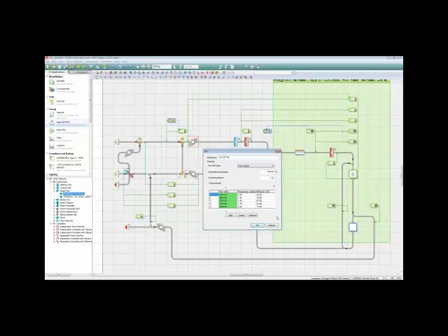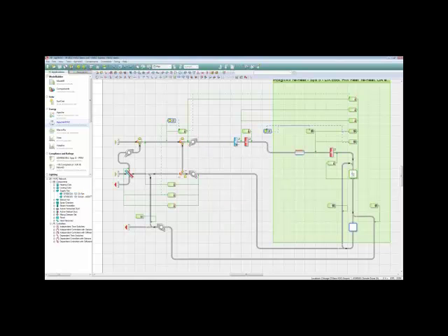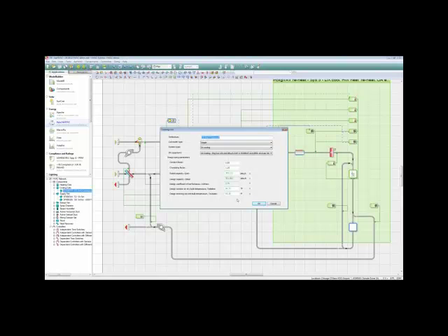So all of the coil sizing is done directly from the process that we just went through, as is the fan sizing. So if I go in and look at this DX coil, for example, it's now got these values, and as I pointed out before, these are now the design conditions for the design sizing of this coil, and you can see that here's the rated capacity at the rated conditions, and this is derived from what I've got in the types dialog as defined for this type.